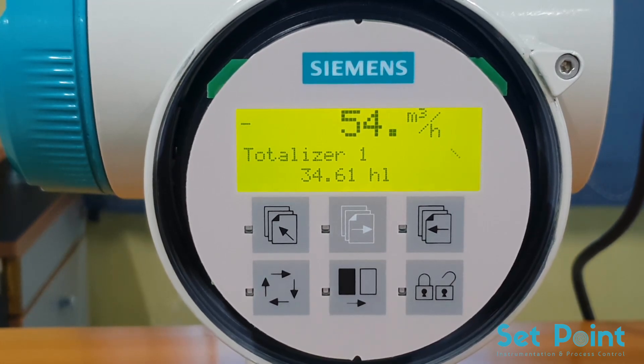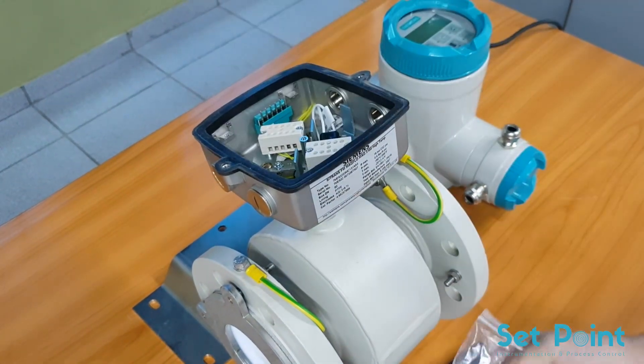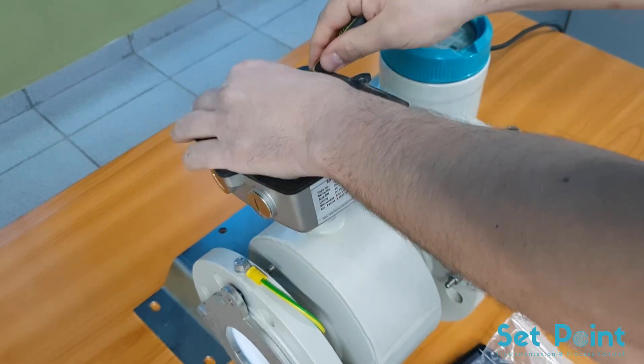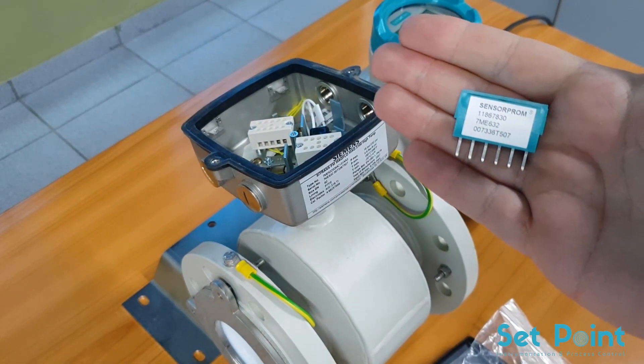The larger number on the display is the flow rate and the smaller number is the totalizer value. Now I will show you how to program the MAG-6000I transmitter, especially if your SensorProm has been lost or damaged. Recall that every MAG 5000 or 6000 based flow system has a factory-supplied SensorProm that is shipped with a flow tube. The SensorProm contains the calibration and size data for that particular flow tube.